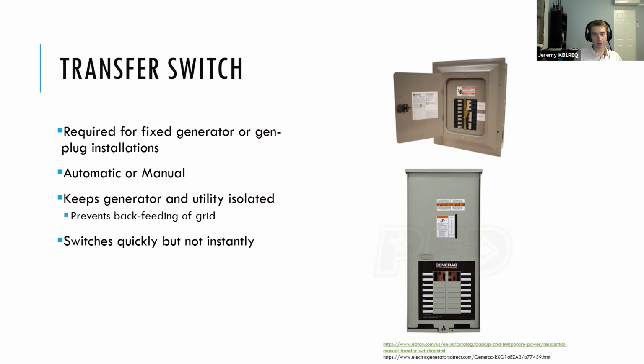The manual is essentially a series of interlocked circuit breakers, and you have to go in and switch from mains to generator, and it disconnects on the utility side and connects on the generator side. Then when your utility comes back up, you switch it back. An ATS just does that automatically. It's designed, as part of a fixed generator solution, to sense loss of utility and start up that generator. When that generator has come up to its running voltage, it brings the load on. An ATS switches quickly, it switches automatically, but it's not instant.